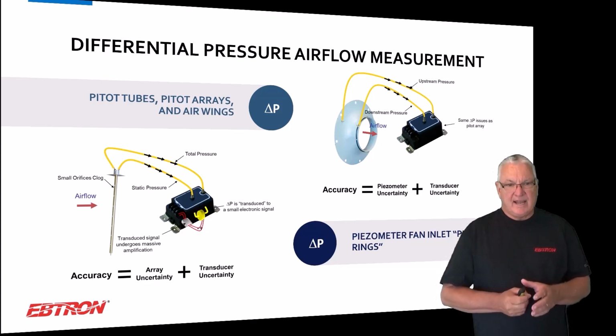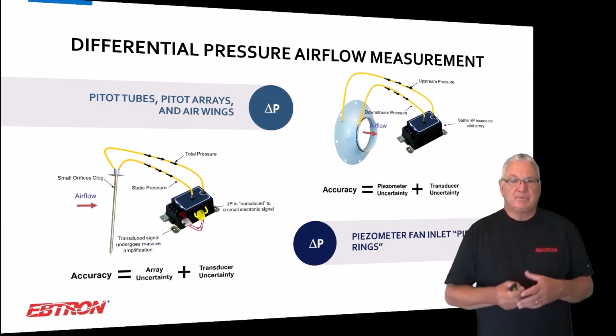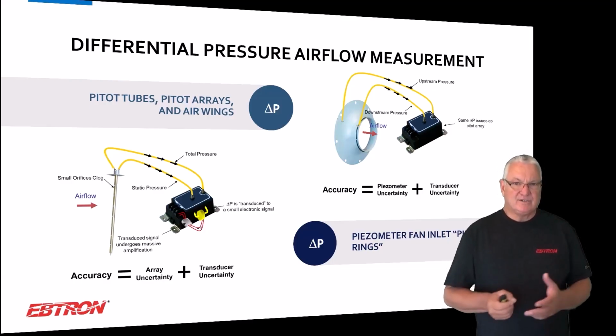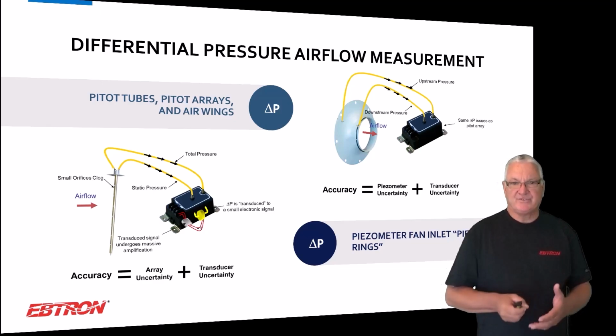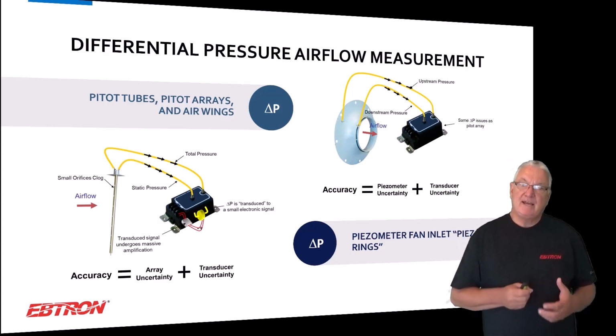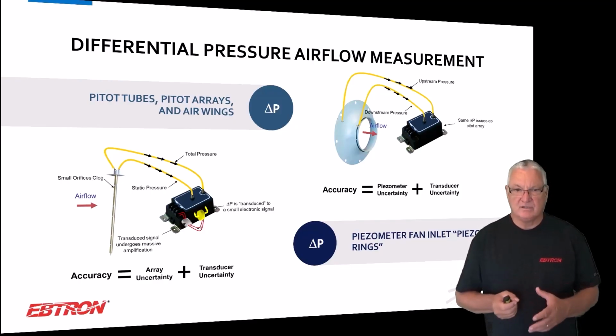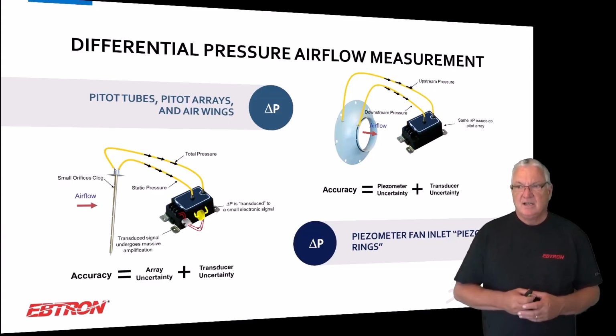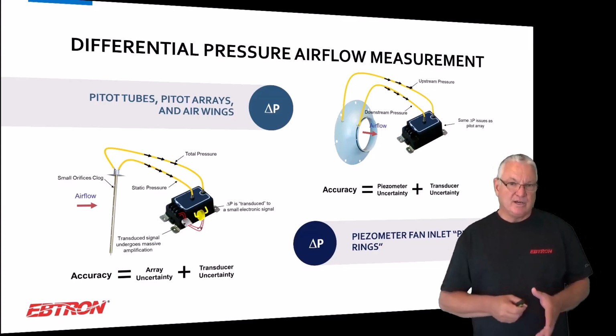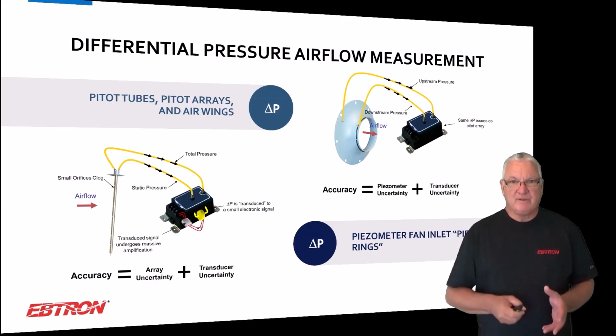And you have to understand that the accuracy is a combination of the uncertainty of the array and the additional measurement uncertainty of converting that differential pressure signal to the airflow rate. The same thing's true with piezo rings. The only real difference with piezo rings for fan inlets is that the pressures are higher. But when you look at the pressure sensors that are used, really the accuracy classes are all about the same as you're using on DP. The turn down's the same, and actually the effect is about the same. And when you're doing a piezo ring, you're using the inlet cone as the fixed orifice flow meter, and every inlet cone is a little different. They're not precision machined devices, so the flow coefficients from one to another vary. So there's measurement uncertainty there.